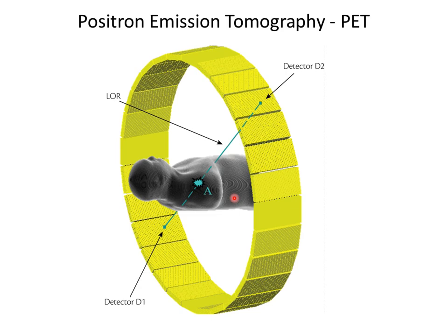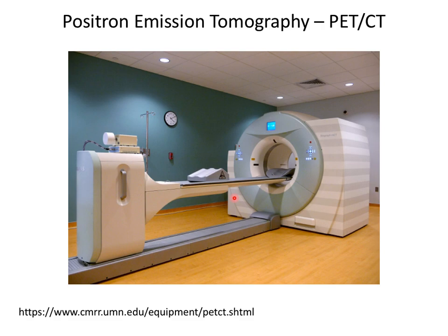There are many ways of reconstructing this data, but one way you could do it is put it into a classic tomography projection geometry and do back projection. But normally, just a big old least squares fit is done on this data. So this is what a PET CT scanner looks like. The CT part is here, and you make a CT image of the patient, and then you put them in the PET section and just integrate up your counts, and you use the CT part to do that attenuation correction on your data. Okay?